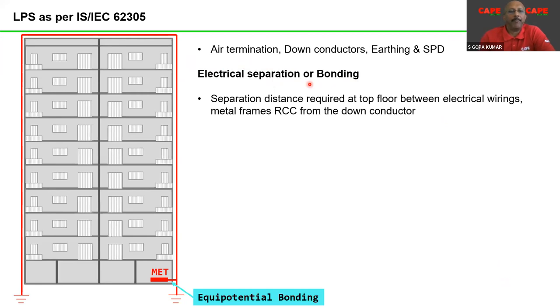What is electrical separation? Electrical separation means the separation distance required at the top floor between electrical wiring, metal frame, and the down conductor. It means the parts of the lightning protection system must be physically separated, electrically separated, from the structural parts of the building. I have better pictures, I will show you. Always the separation distance is calculated with equipotential bonding at the ground floor. Here you see, with equipotential bonding, in the sense the down conductor and the electrical system are equipotentially bonded.